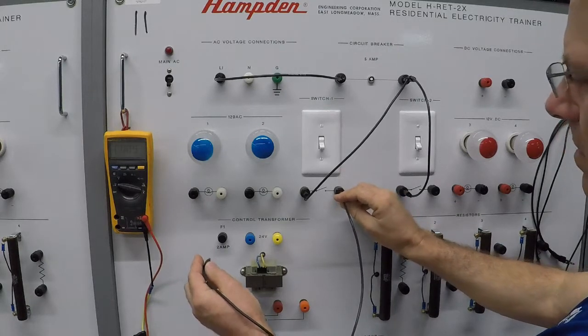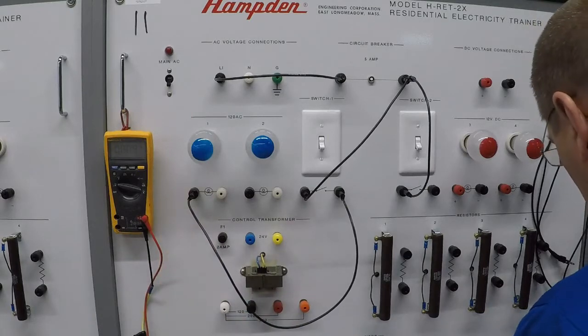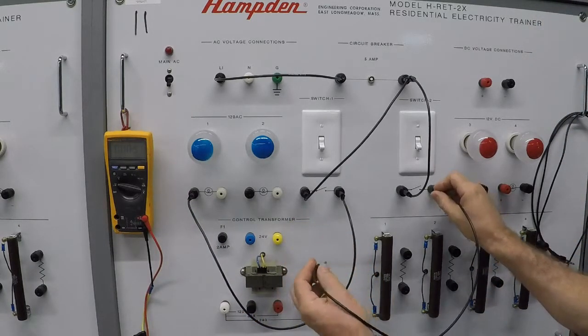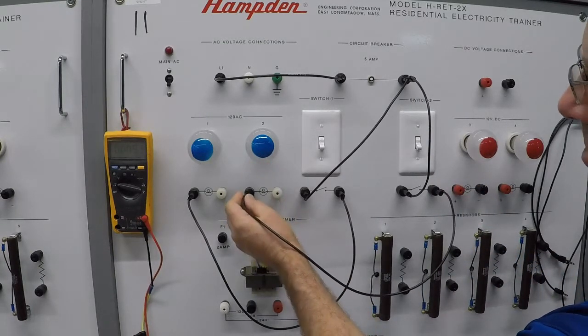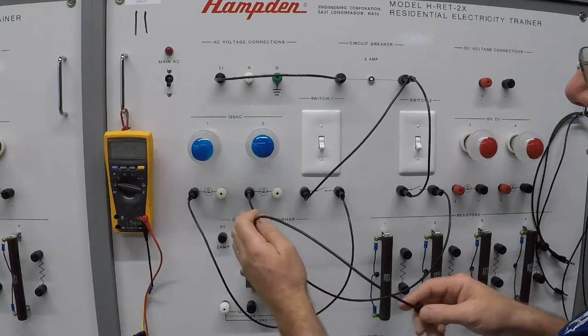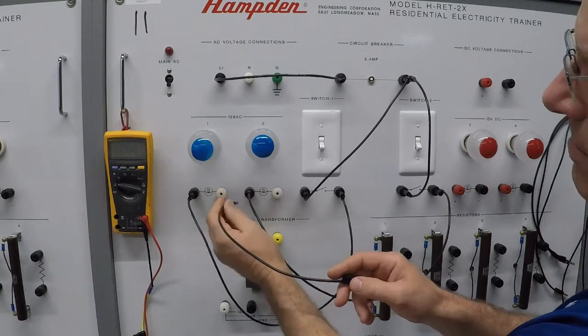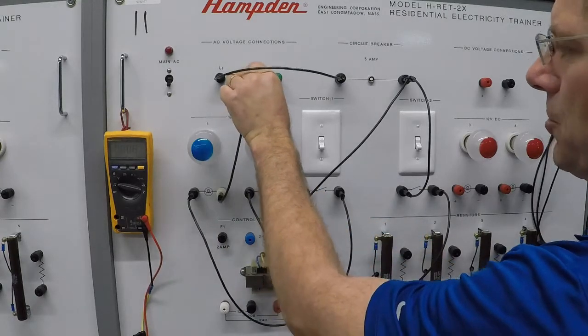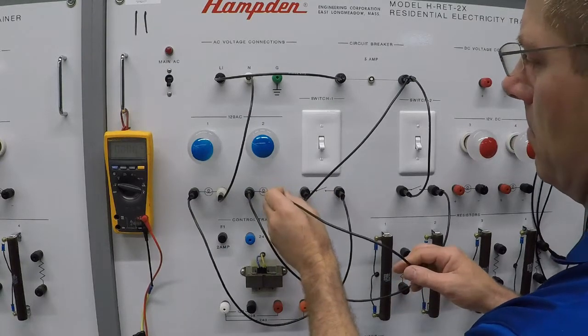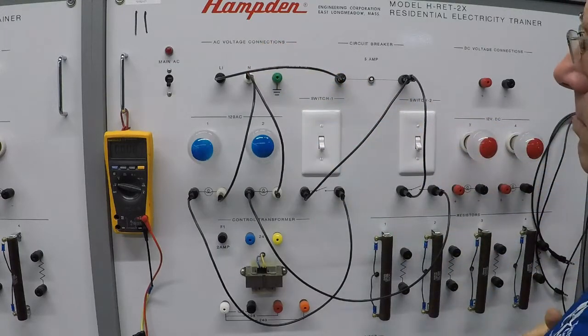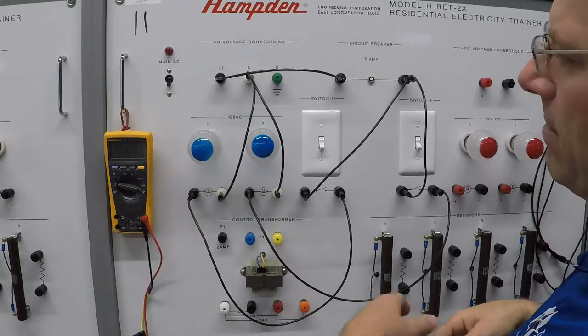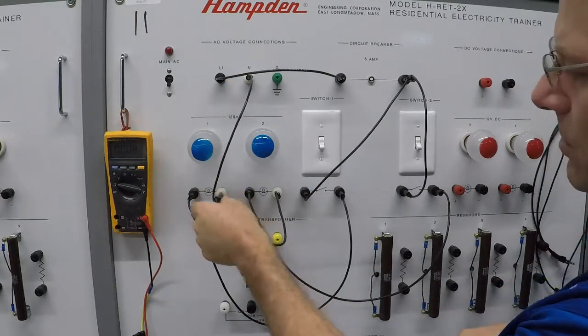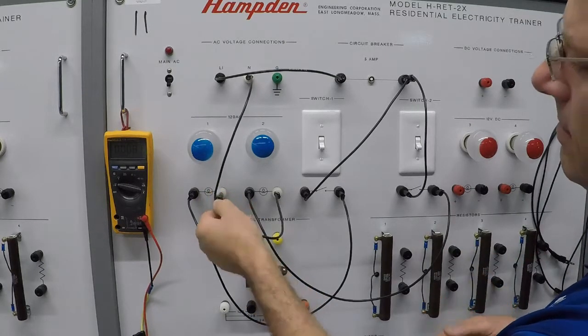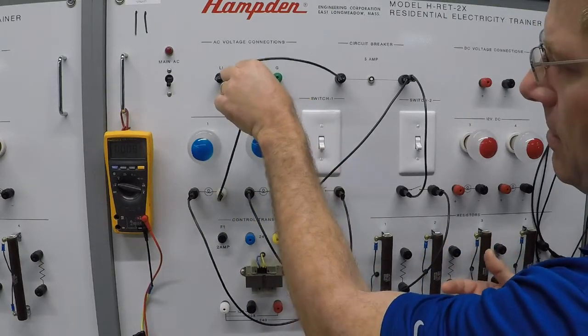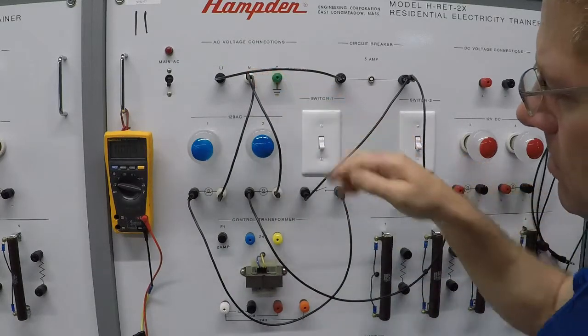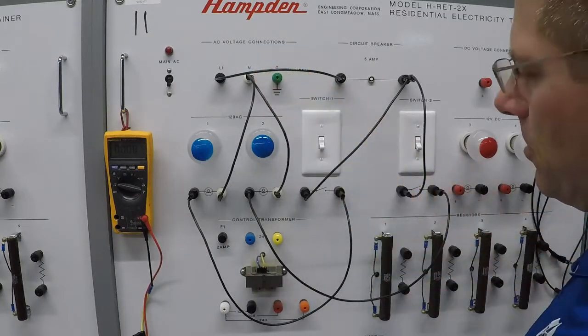From switch 1, connect to L1, connecting to the black terminal. From switch 2, we're going to connect to the black terminal of light bulb 2. From light bulb 1, to complete our circuit, connect the white terminal back to neutral. And we'll do the same thing for light bulb 2, connecting it back to neutral. As an alternate method, you could connect the circuit like this, but for simplicity, for you to better see and understand the circuit, I would recommend connecting back to our neutral terminal, considering this would be a home run shot, as it's referred to.